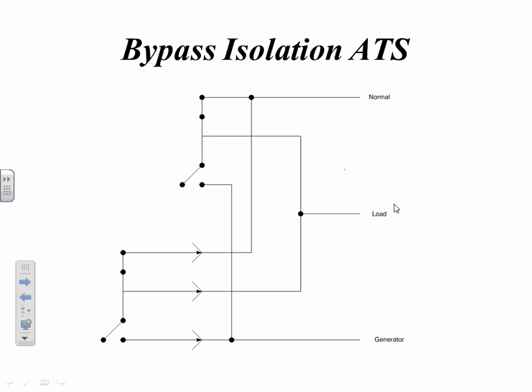So, code was reworked, and we had to, in certain cases, supply bypass isolation transfer switches. Again, we have parallel sets of contactors. If there's a problem, this one can actually be racked out. Let's look at how we're supplying load here. Normal power here comes into the switch, goes this way through the automatic transfer switch to the load this way. Okay. This set of contactors, the manual contactor, is set up the same way. It's actually supplying load power to the load through its contactor, but this one has to be manually operated.